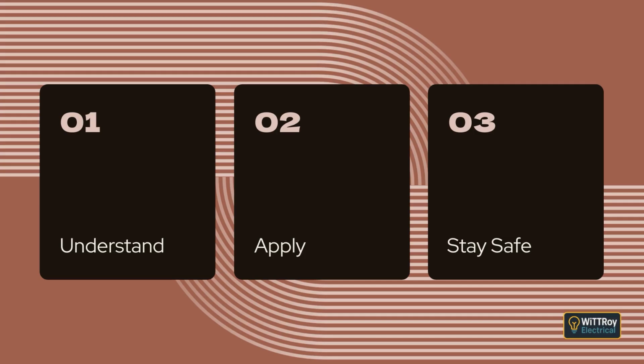Clause 7.4.6 Multiple items of electrical equipment. This clause explains several requirements when a separated circuit supplies more than one item. Exposed conductive parts must be connected together by an insulated equipotential bonding conductor and must not be connected to earth, to protective earthing conductors, or to exposed conductive parts of another circuit. Any socket outlet installed on the separated circuit must have its designated earthing contact connected to the equipotential bonding conductor. The designated protective earthing conductor of any supply cable or flexible cord to the equipment must be connected to the equipotential bonding conductor.